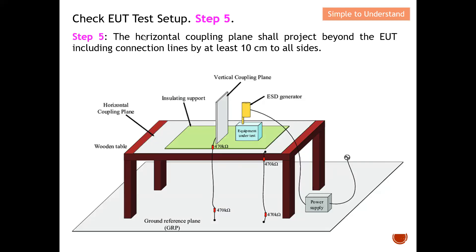Step number five: the horizontal coupling plane should project beyond the EUT — including all connecting lines — by at least 10 centimeters on all sides. If you have a large EUT, ensure it still maintains at least 10 centimeters clearance all around within the horizontal coupling plane.